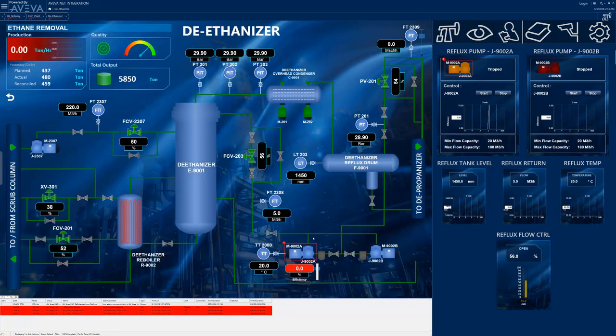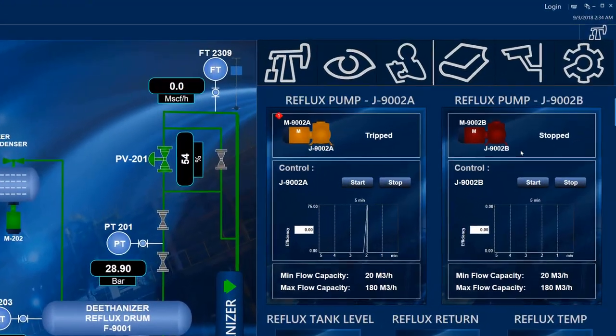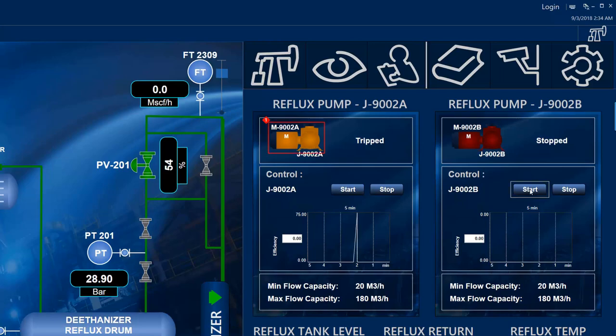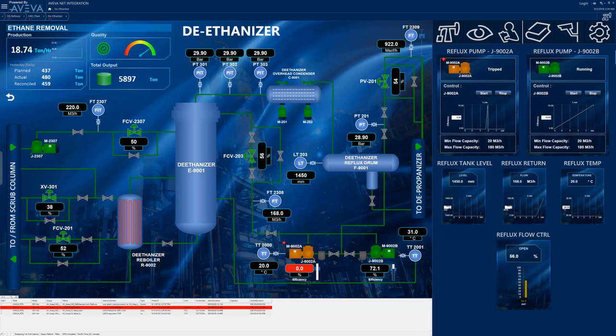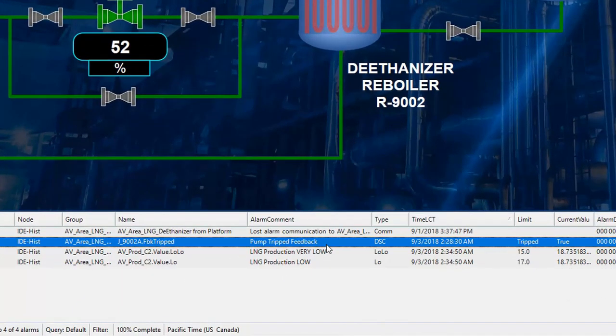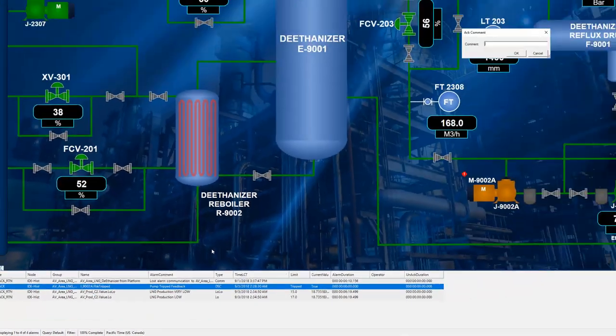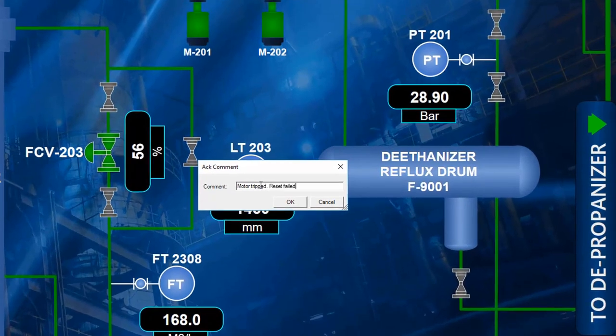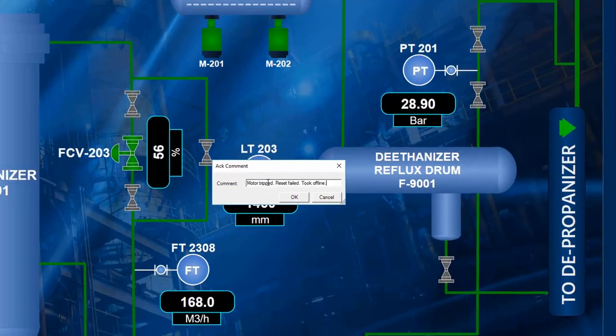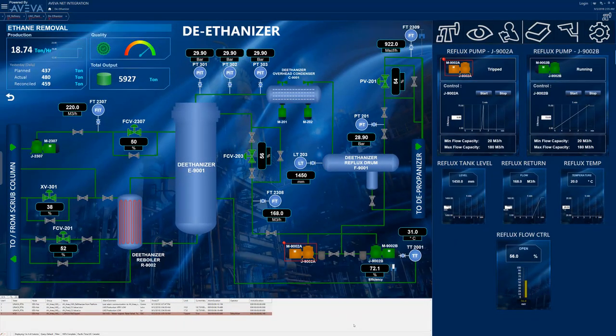The operator returns to the deethanizer detail screen and starts the backup pump. The real-time control system confirms that the pump has started and that production has been restored. Now that the immediate problem has been resolved, the operator acknowledges the alarm, adding a note about their diagnosis and resolution. Notice how the red alarm border surrounding the failed pump has stopped flashing. While the pump is still in alarm – it's tripped – it's lower severity now, because the operator has acknowledged the alarm.